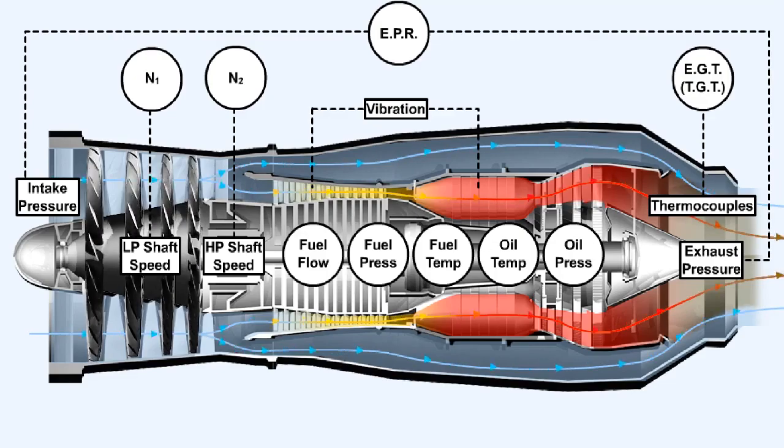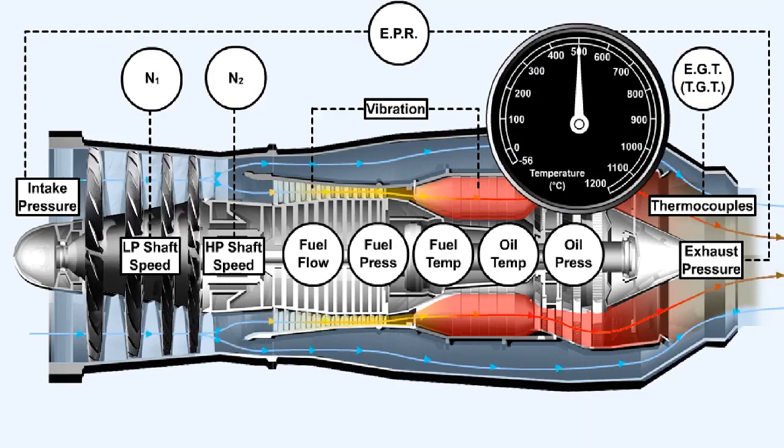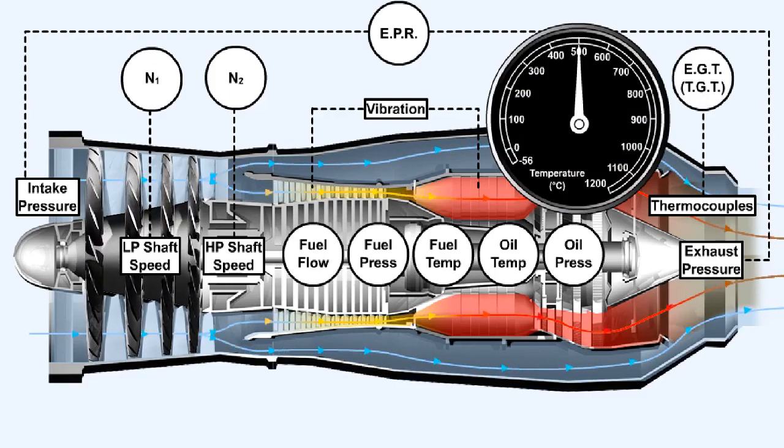The following temperatures are monitored on gas turbine engines: engine air inlet temperature, exhaust gas temperature, engine oil temperature, and internal air systems temperature. The temperatures monitored may range from minus 56 degrees Celsius to plus 1200 degrees Celsius. Different sensors are used depending on the temperature range to be monitored.